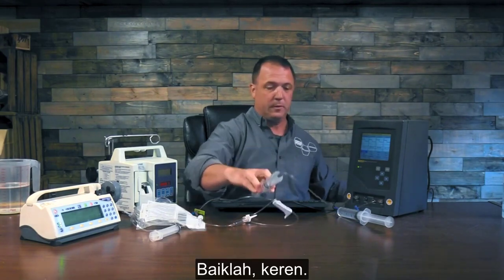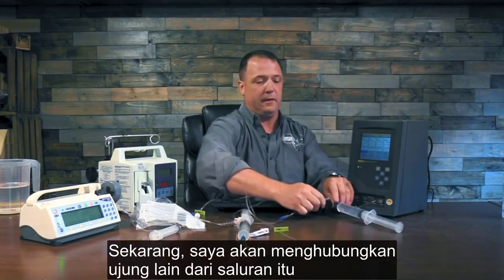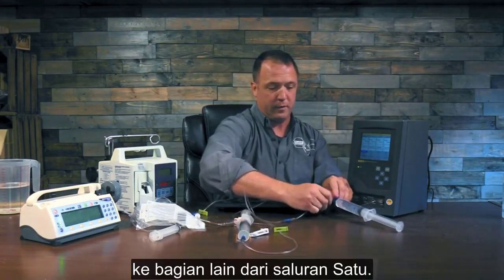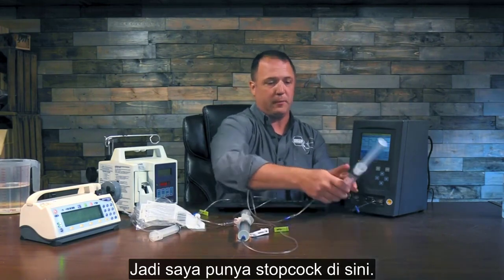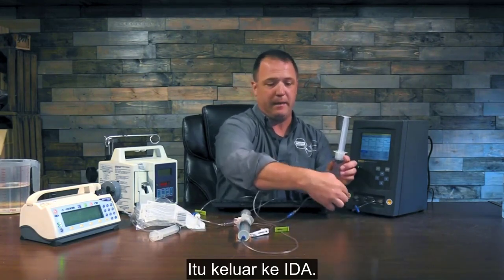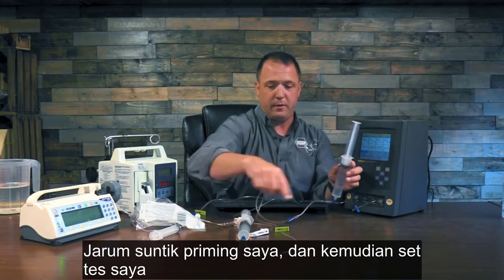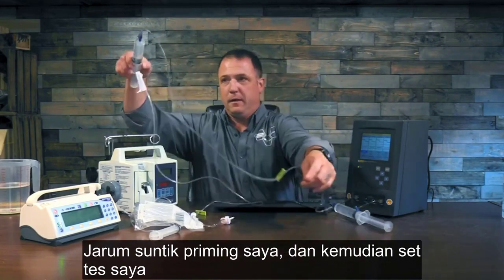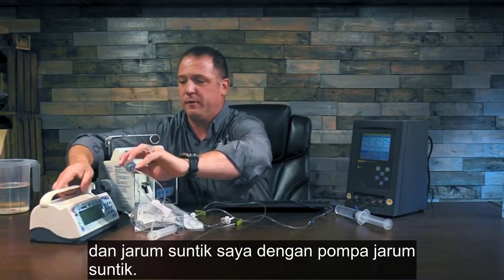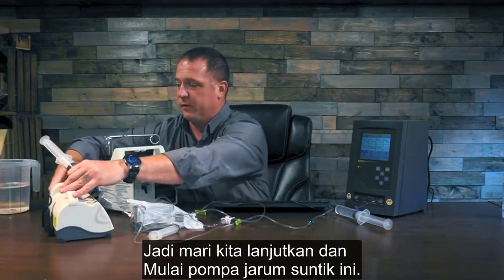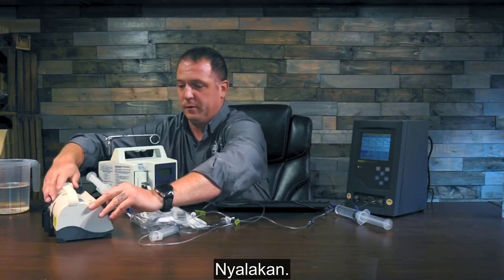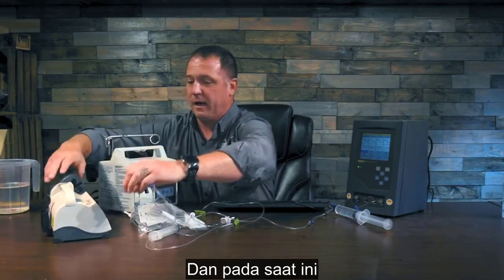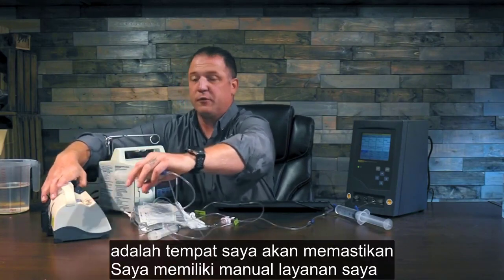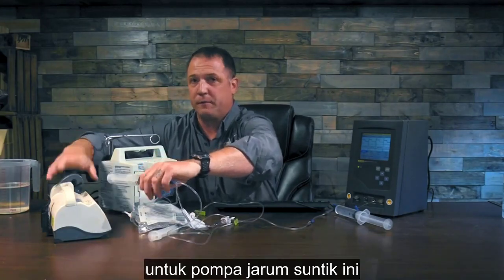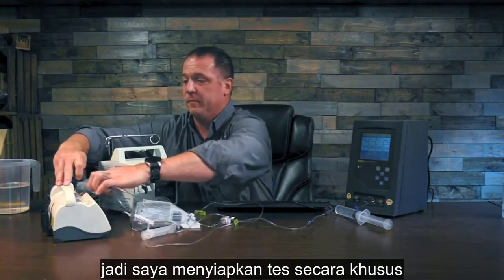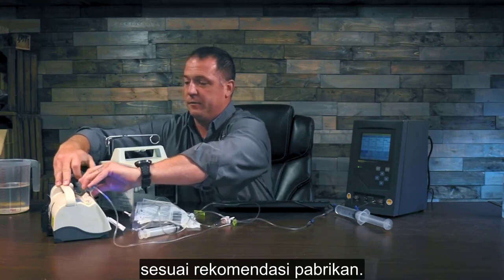All right, cool. Now I'm going to hook up the end of that line to the other portion of my channel 1. So I have a stopcock here, it goes out to the IDA, my priming syringe, and then my test set, and my syringe I'm going to run with a syringe pump. So let's go ahead and start this syringe pump. Turn it on, and at this point in time is where I would make sure I have my service manual for the specific syringe pump, so I'm setting up the test specifically as per the manufacturer's recommendation.